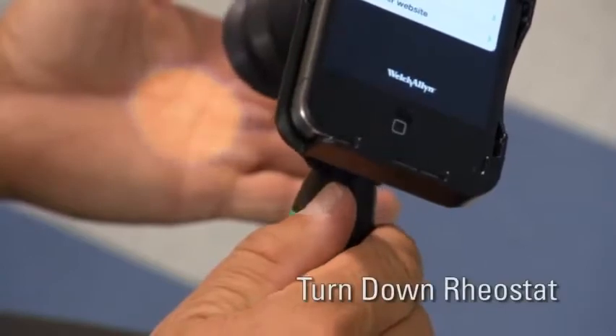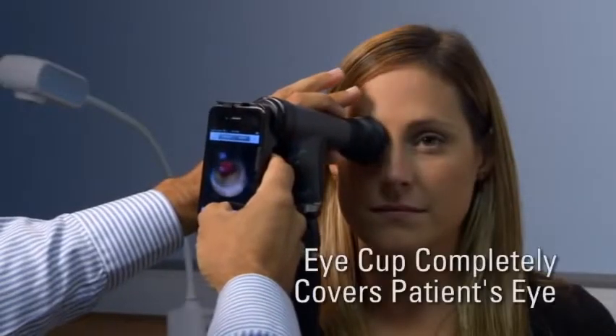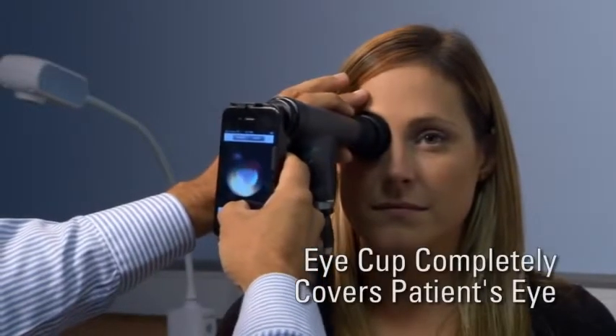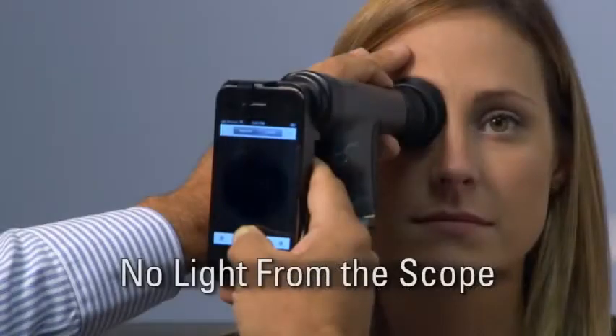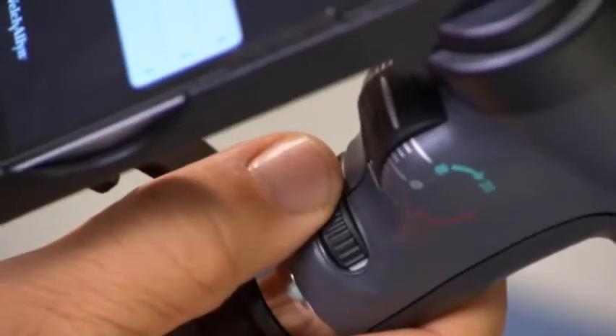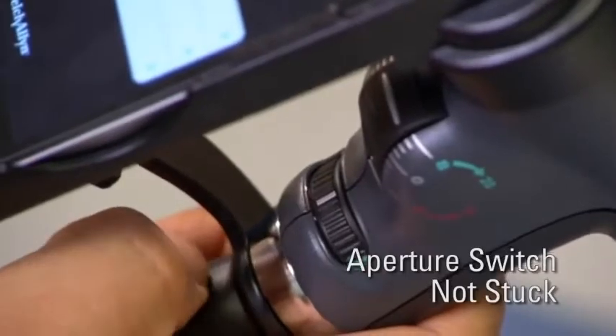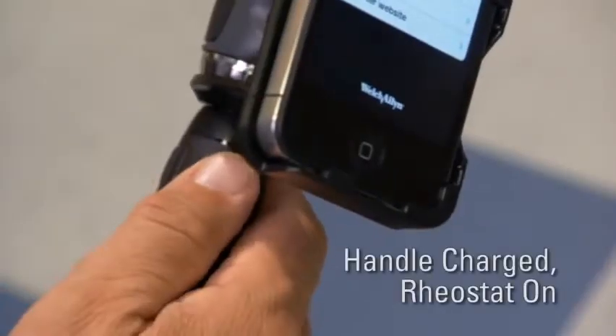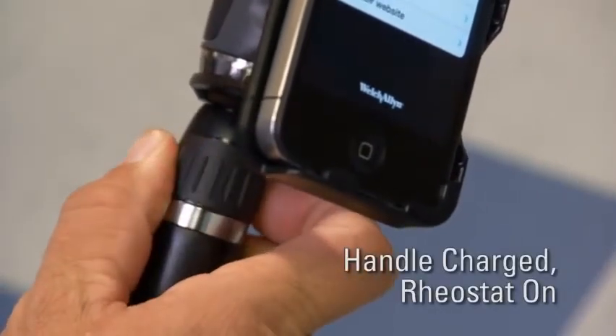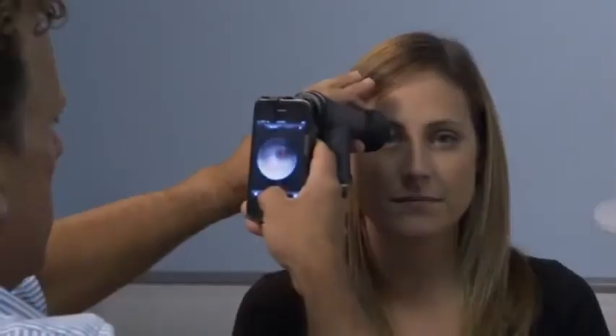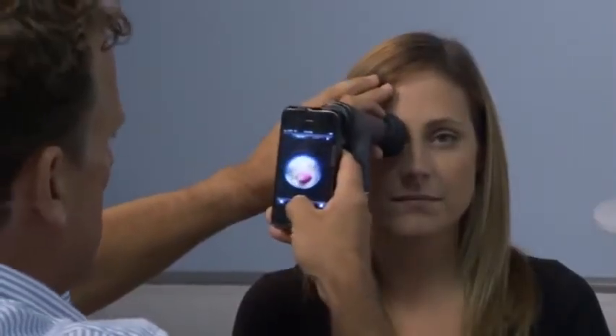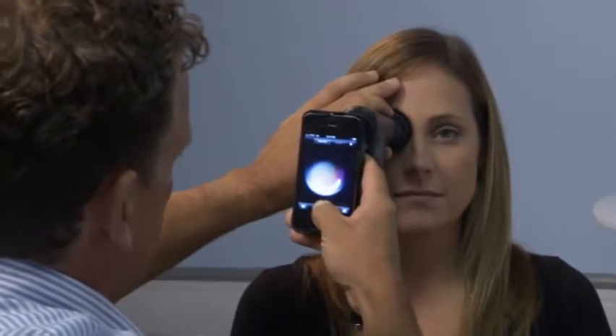Turn down the rheostat on the handle. Make sure the eye cup is completely covering the patient's eye. If no light is coming from the scope, make sure the aperture switch is not stuck between apertures. Make sure your handle is charged and the rheostat is turned on. Remember that practice is the key to becoming proficient.